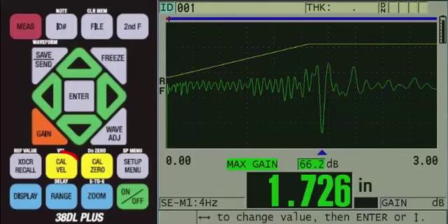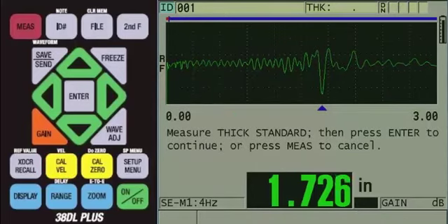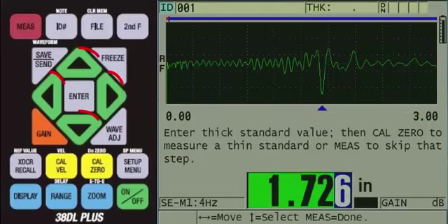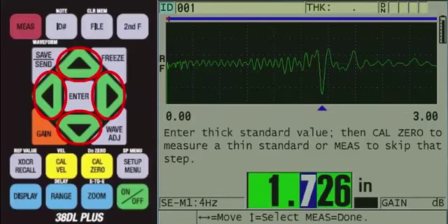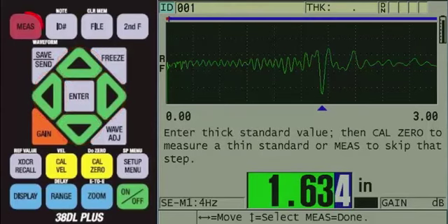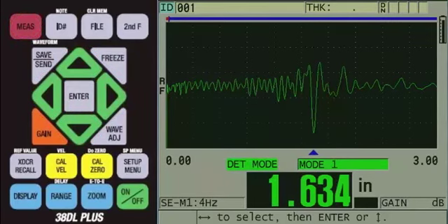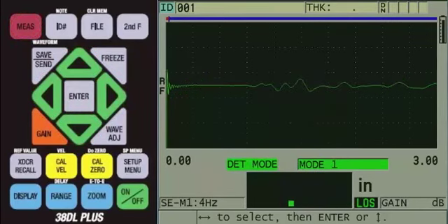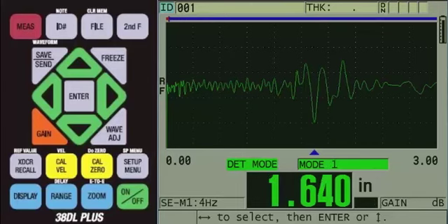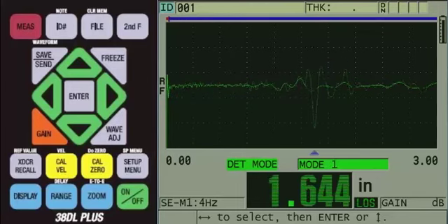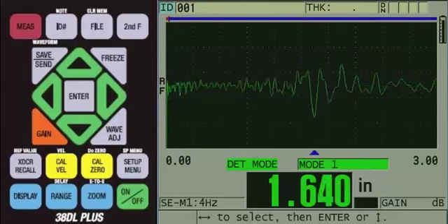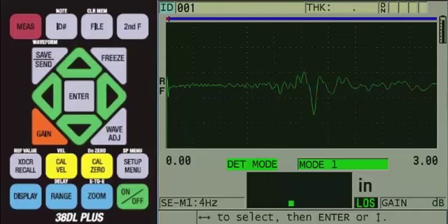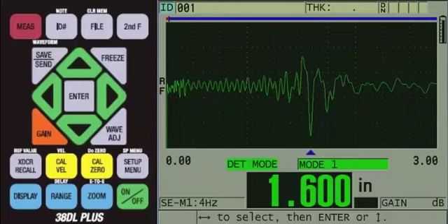To do this, we will first press the yellow Cal-Vel key and then couple onto the sample. Once you have a steady reading, press the Enter key. Then use the arrow keys to change the value to 1.634 inches or 41.5 millimeters. Then press the red measure key. You'll notice variations in thickness when measuring from point to point on the same sample. This was discussed in previous slides and is caused by variations in the ratio of fiber to resin within the sample, which in turn causes changes in the time of flight measurement and thus the thickness reading.